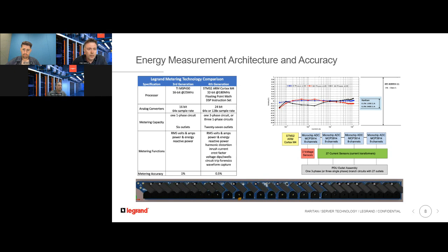And our new in-house developed 3-phase embedded power supply also utilizes the new metering circuitry for 3-phase inlet metering, as well as for circuit breaker trip detection. The same firmware architecture is also used on both the inlet and outlet metering chips, which allows us to provide the same metering features on the AC inlets as well as on all the PDU outlets.